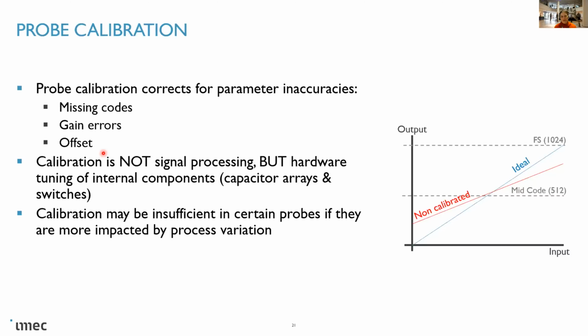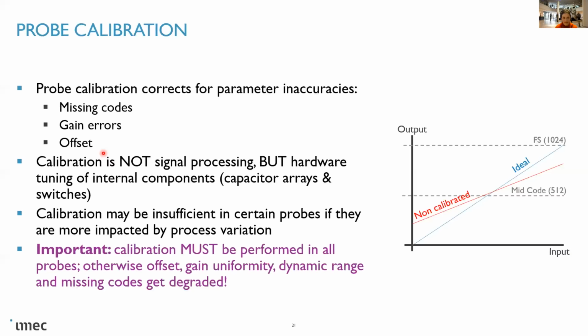It can also be that the calibration is not sufficient to fix certain probes. If the probe is very bad, we will never put it on the market. That's not what we will do, but you may get probes that have some channels that are maybe more noisy. So it's important that this calibration is always applied. Although it's an option, you will receive the file and it's up to you whether you use it or not. We really encourage you to calibrate your probes. I believe all the software that is now available takes those files into account. So I think it should be a little step that you do before every experiment to apply this calibration.